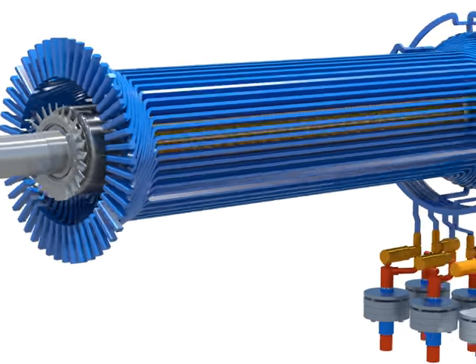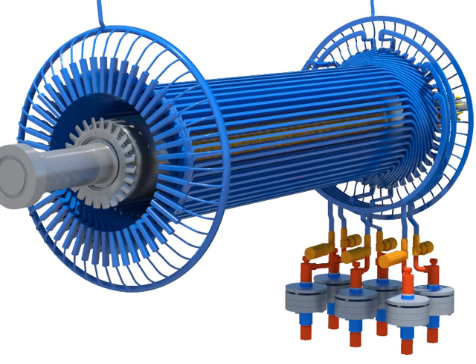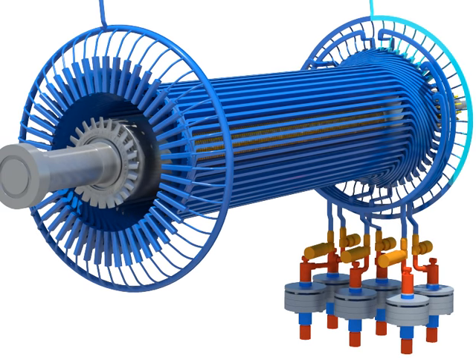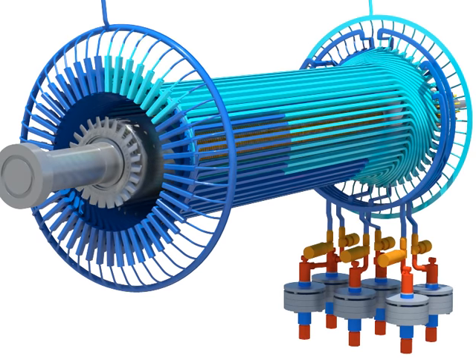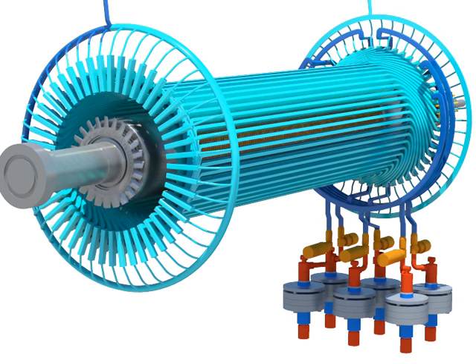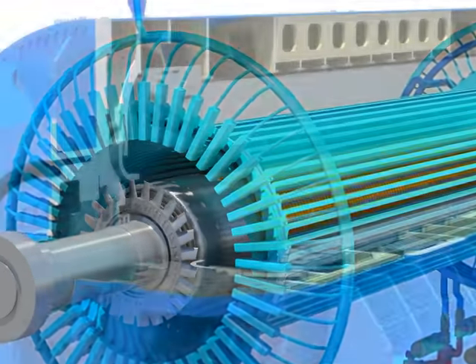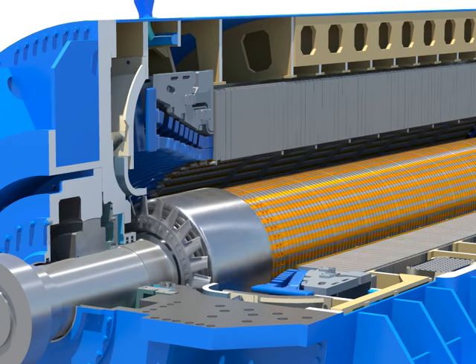For generator cooling, the stator winding adopts a cooling method using water and the rotor adopts a hydrogen cooling method. Circulation of hydrogen is done by the axial flow fan attached to the rotor shaft inside the machine.